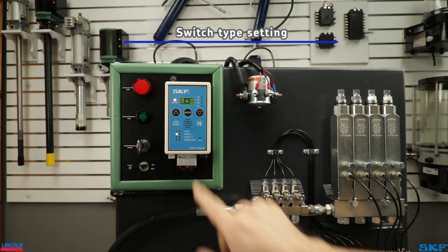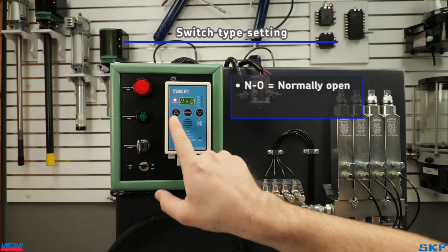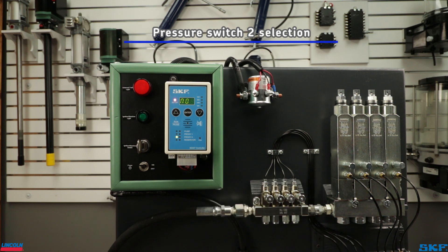The next setting after timeout is the switching state of the pressure switch. N-O stands for normally open; N-C stands for normally closed. In my system's case, the pressure switch is normally closed, so we will change the setting and move to the next screen, which will then ask if a second pressure switch will be used. There is only one pressure switch in this system, so we will leave it at no.